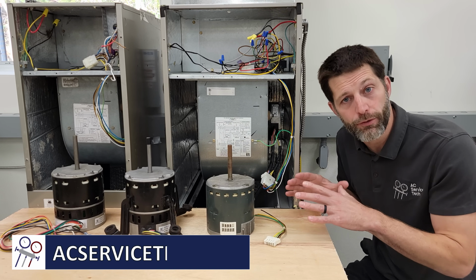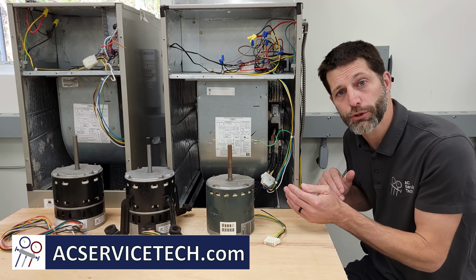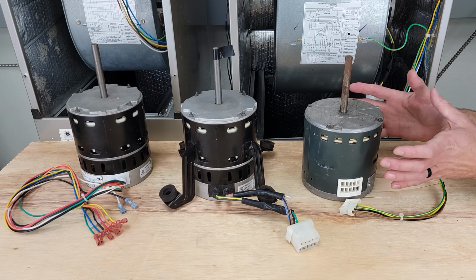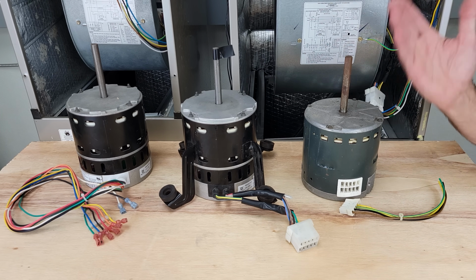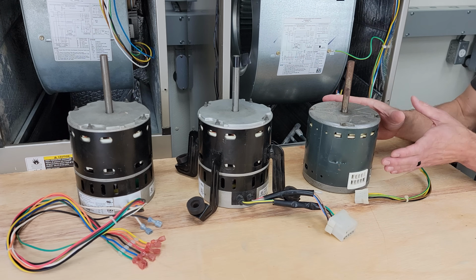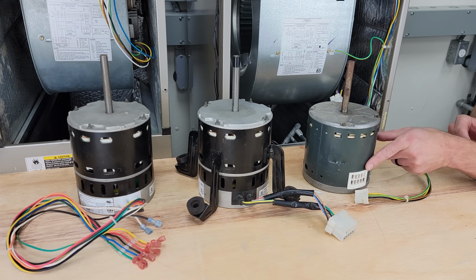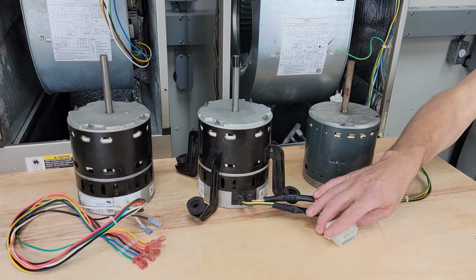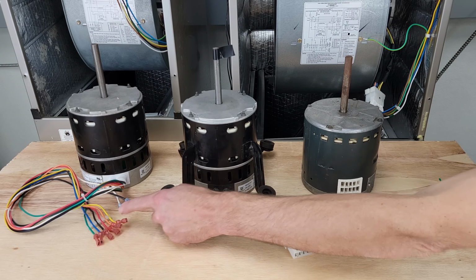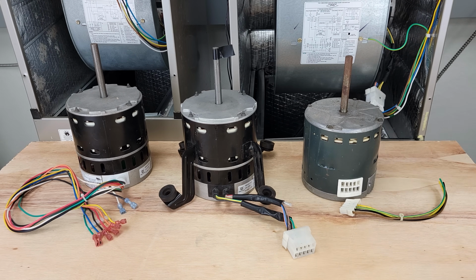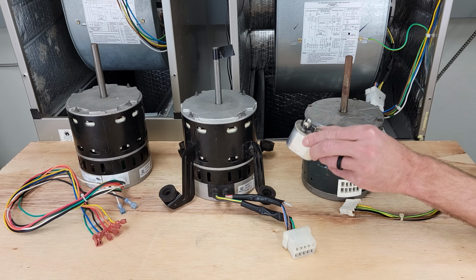These ECM constant torque blower motors are really easy to troubleshoot, and I'm going to show you how on an actual unit. These types of blower motors are becoming very popular on air handlers and on gas furnaces. And you can tell if you have one because you'll see Spade connectors on the shell of the motor or on the end of the wires or on the end of the individual wiring coming off the blower motor, and you don't see an externally mounted capacitor.